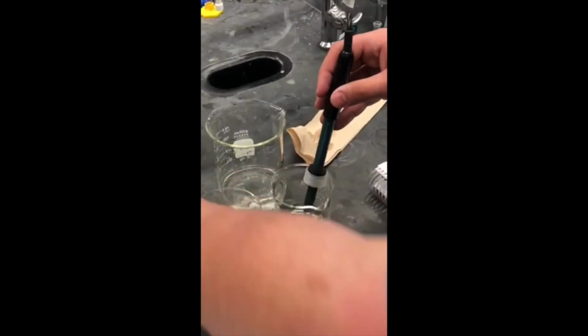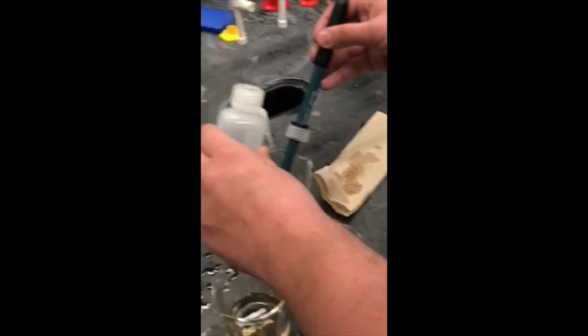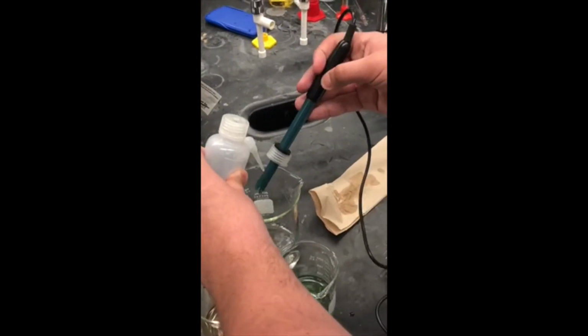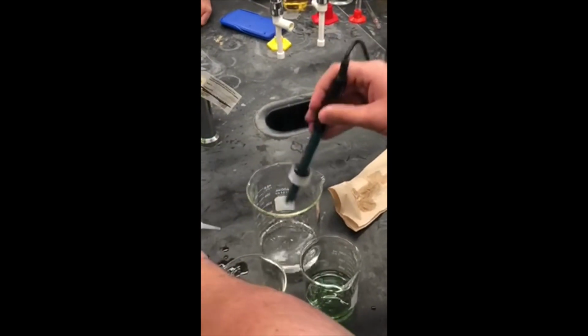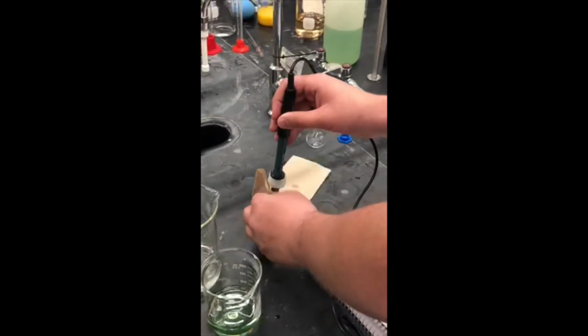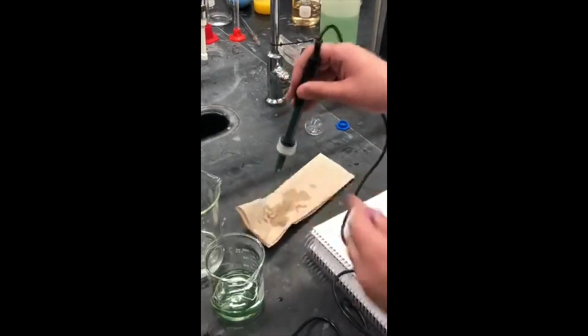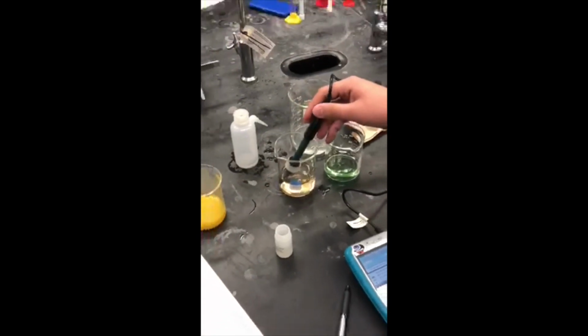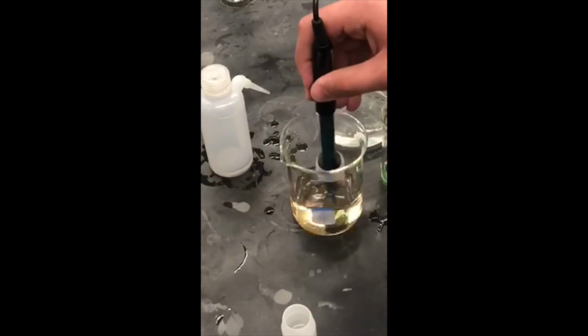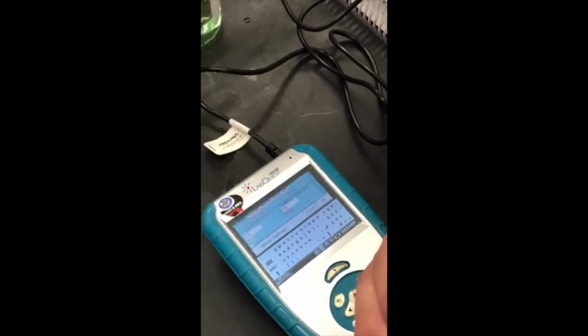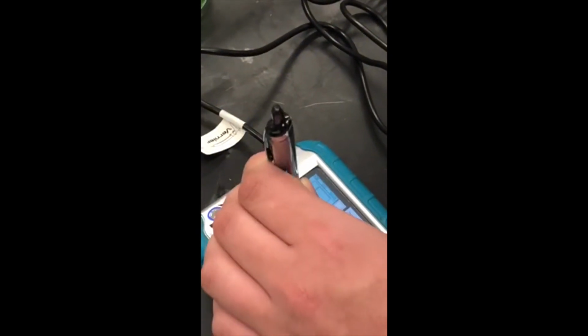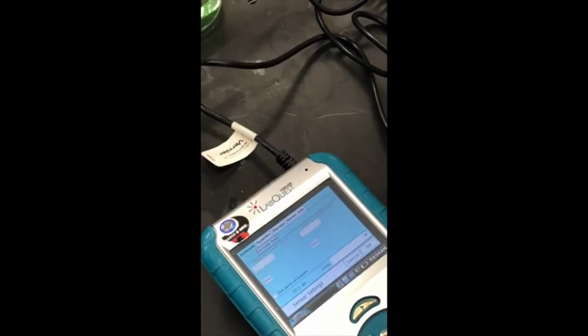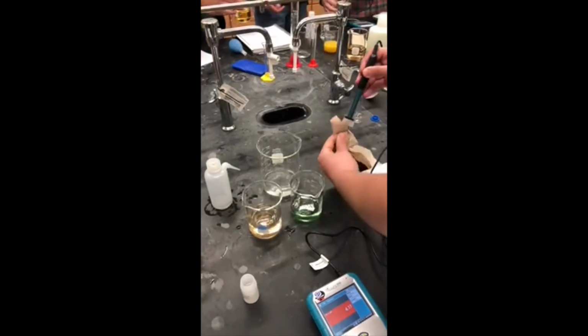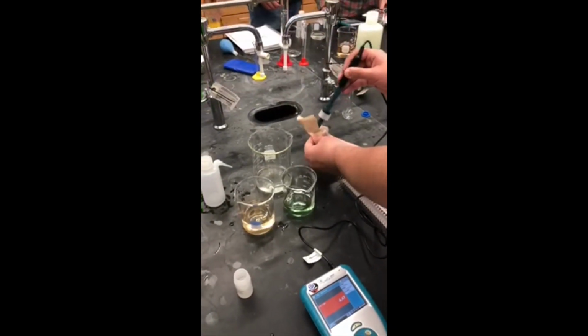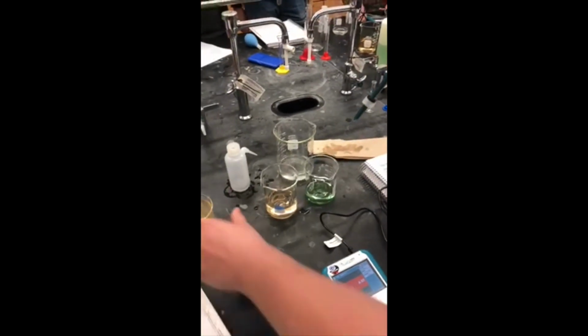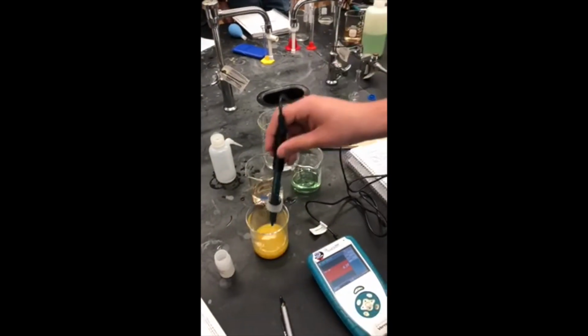Alright, then I'm going to take this out, rinse off the pH 7 buffer from there, dab off the water from here. I'm going to throw that into the pH 4 solution, stir it around real quick, wait for the voltage to be constant, looks like it is. Hit keep. We're going to clean it off once again, get the water off one last time before we come over and we measure the pH of the orange juice.